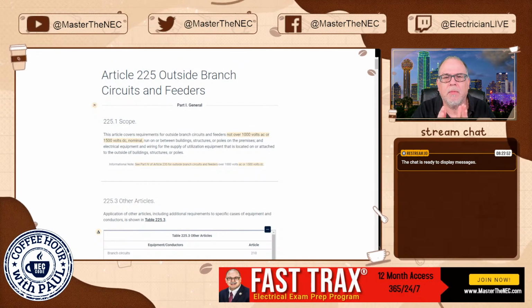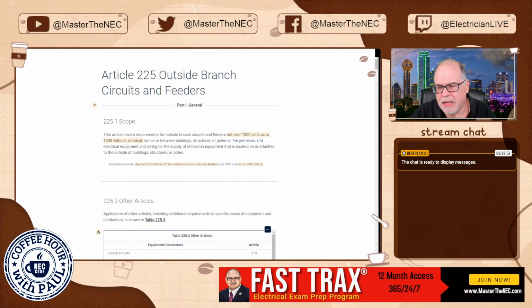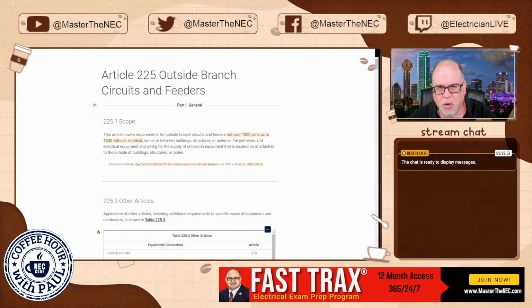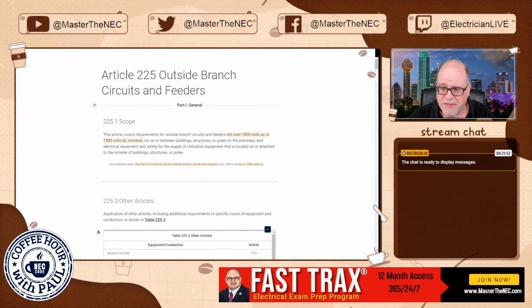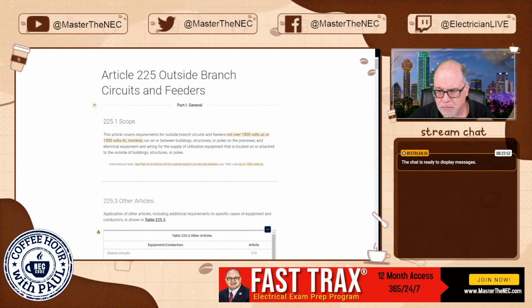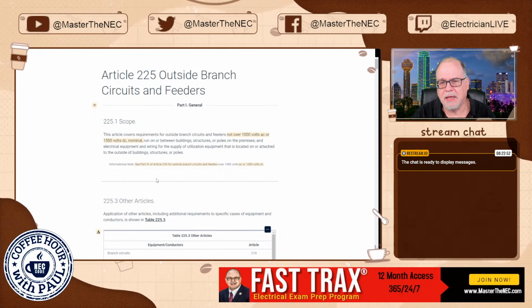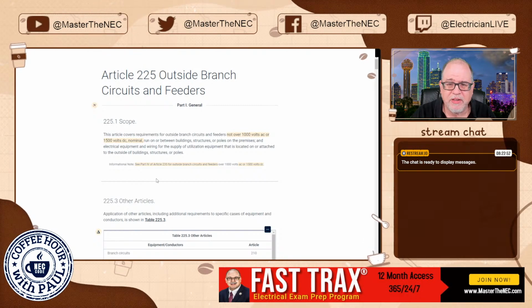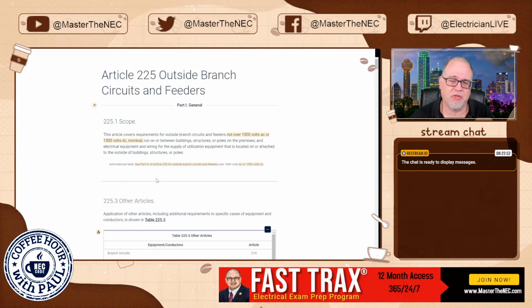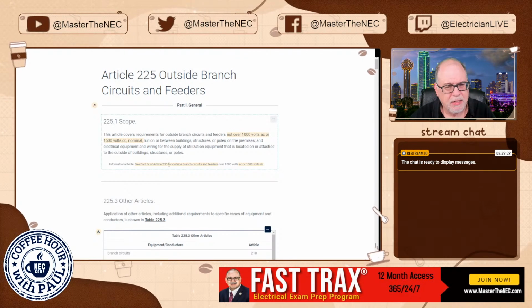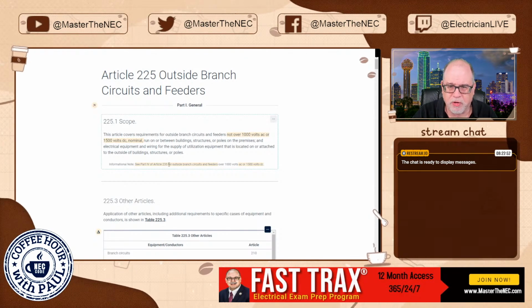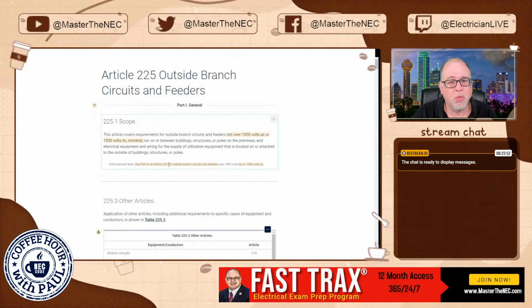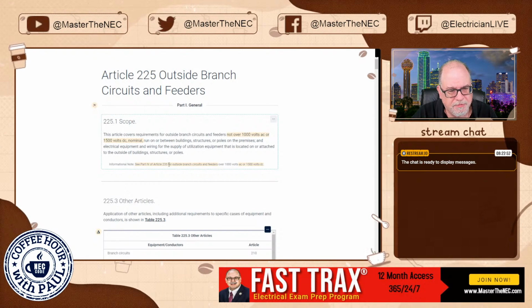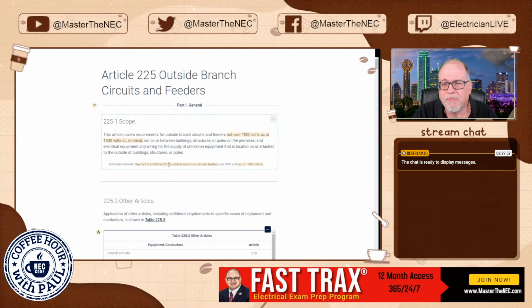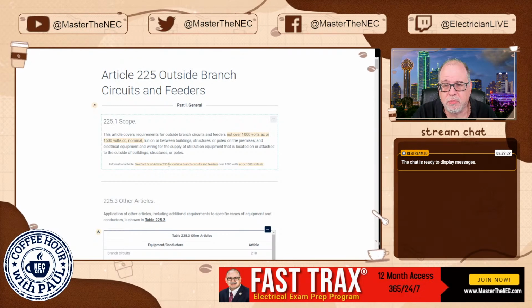Also, anything that's dealing with over 1,000 volts has now been removed from 225. It's now going to be in 235. So that is significant as well. So when you're dealing with over 1,000 volts, then you want to go to Article 235. So that's a new article for the 2023 edition of the National Electrical Code.